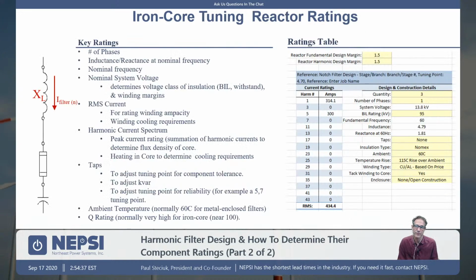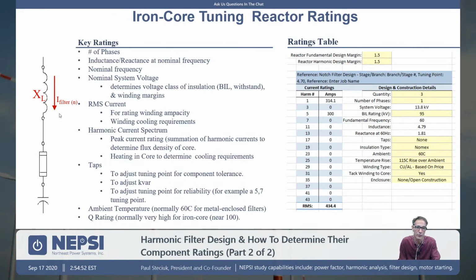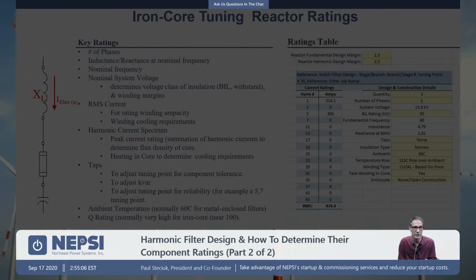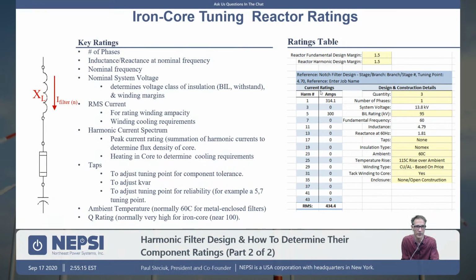So for the process of specifying the reactor itself, we use a spreadsheet tool again. The harmonic analysis program is coming up with a harmonic filter current, and from there we decide what we want to rate the harmonic filter at, and then we calculate how much harmonic current flows into the reactor, and we specify the reactor to the supplier. So what I show here to the right are the key ratings that we would typically use. Let me see here. There we go. We will show what we're transferring to our reactor supplier. So it's a pretty simple process.